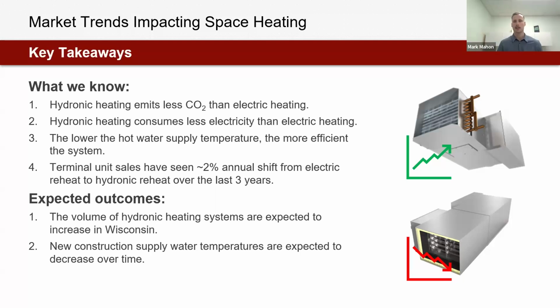And then a peek behind the curtain: I can tell you guys, over the last 3 years, I see terminal unit sales shift about 2% annually from electric reheat shrinking to hot water reheat growing, when we look at the proportion of those two different options being used. So hydronic is increasing in its growth rate. The expected outcome here is we should see more hydronic heating, especially, I think, in colder climates. So I think for Wisconsin, that's definitely true. And I'll continue to expect to see a decrease in that hot water supply temperature over time.